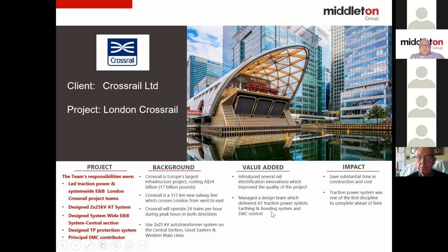I introduced a number of innovations. This is the first metro system underground that adopts a 2 times 25 kV AC system using ROCB, rigid overhead conductor bar. And it is also the first metro system that connects to the national grid of 400 kV supply, allowing regenerative braking to the source. That was the first time as well. And the system is very receptive to train regenerative braking. It was so receptive that we can actually save 30% of the energy consumption, recycling the braking energy.